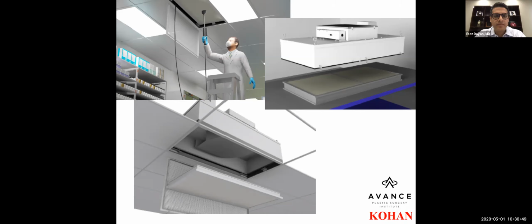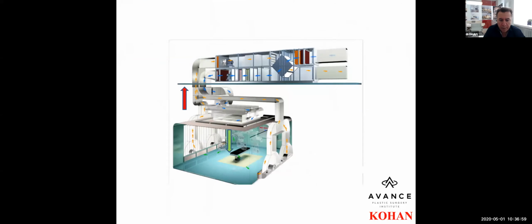I got it. Or if there are windows, air comes in, or outside air may be sucked in. If you're next to a highway, you have more dust and particles coming in. It all depends on that. So that's how it works, actually. This is the HEPA filter system, and that's how it works. It sits on the top of your operatory, your OR, your exam room. It doesn't matter what it is, but this is the actual system. And that's how it cleans it.